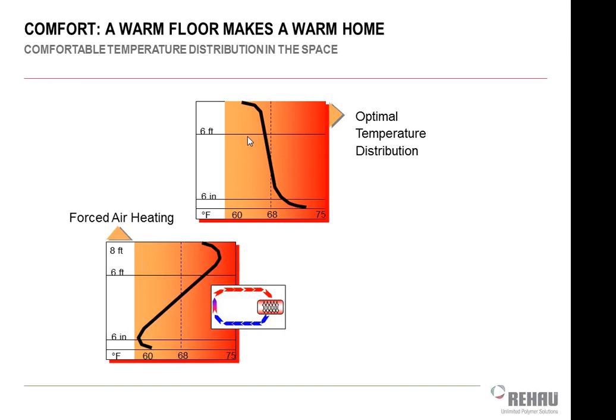So if we diffuse it at the ceiling, especially if it's very hot air that we're diffusing above, say, 90 degrees, which most commercial buildings do, that air will have a tendency to stay up at the ceiling, and you're going to end up with very high temperatures up there versus very cold temperatures at the floor. Like this chart is showing you here, you might have whatever 73, 74 degrees up by someone's head, and then down at the floor you may have 55, 58 degrees.